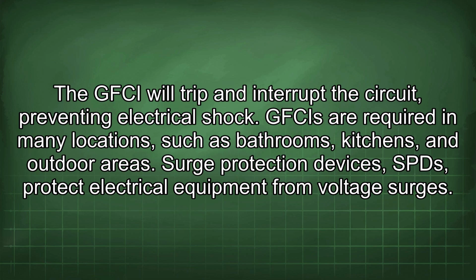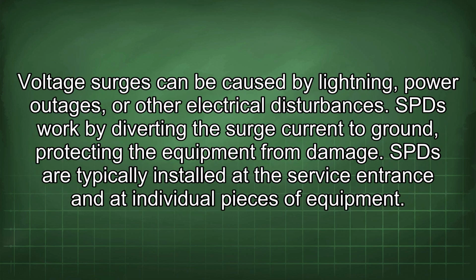Surge protection devices, SPDs, protect electrical equipment from voltage surges. Voltage surges can be caused by lightning, power outages, or other electrical disturbances. SPDs work by diverting the surge current to ground, protecting the equipment from damage. SPDs are typically installed at the service entrance and at individual pieces of equipment.